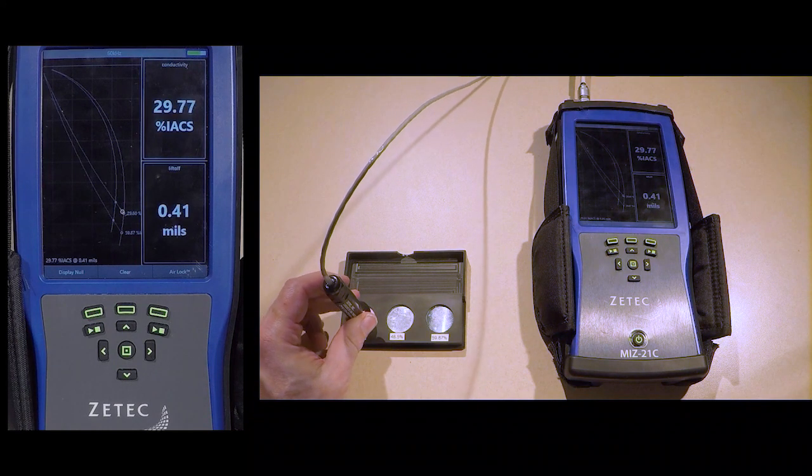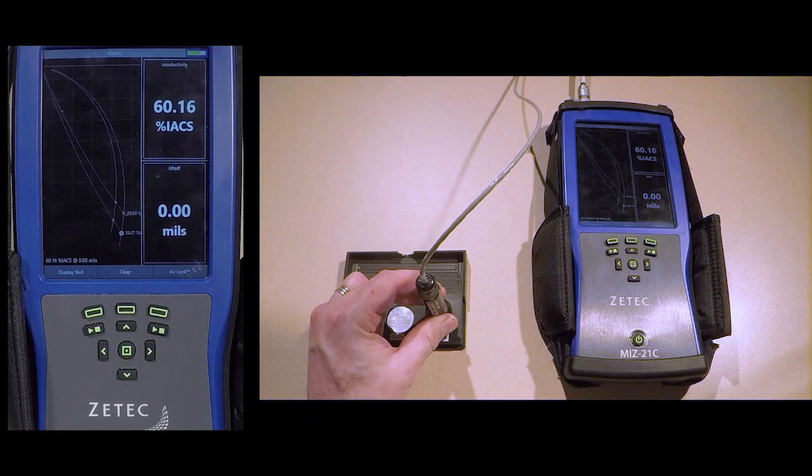Knowing the type of material is necessary to get accurate readings. For convenience, typical material IACS specifications can be found on the instrument, which will be shown later. Normal operation is the same as testing the standard. Apply the probe completely to the surface of the test specimen to obtain the IACS and coating thickness reading if valid. Compare this reading to the material IACS test specification.